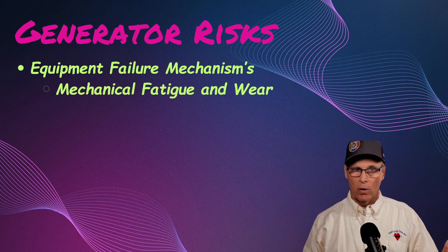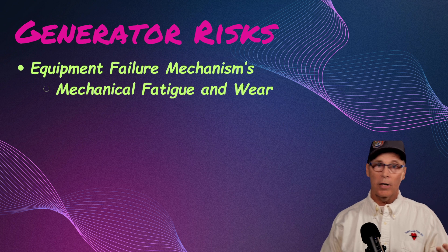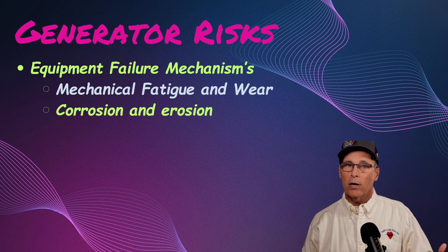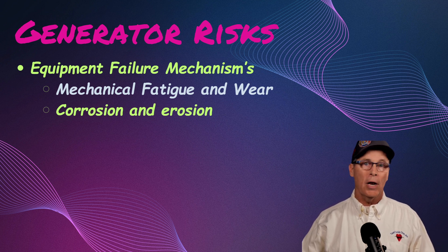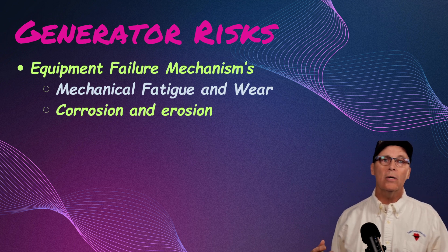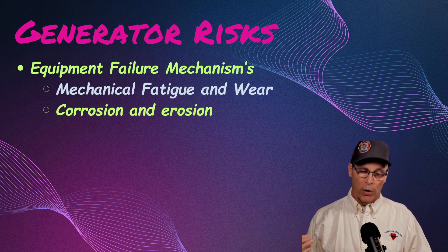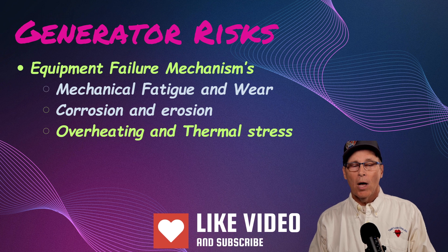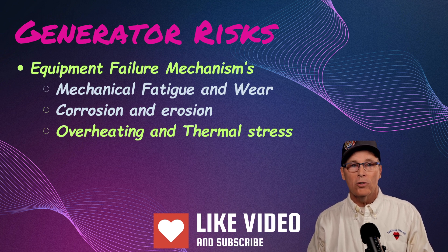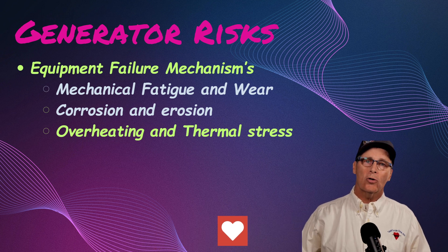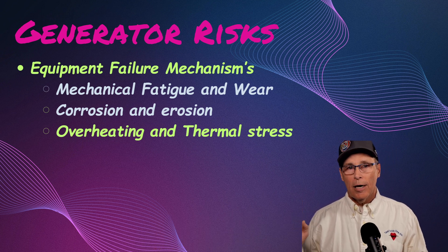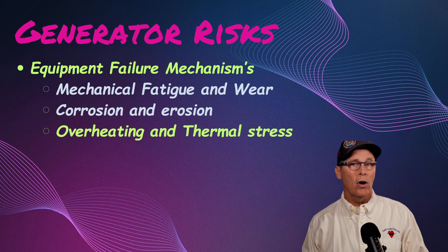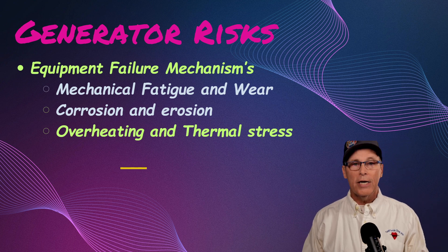Other causes of damage: mechanical fatigue and wear — every time units start up and shut down, they heat up and cool down and need to do so evenly. Corrosion and erosion — air-cooled units draw in lots of air, which can cause abrasion from dirty air, or corrosion from salt air near the ocean. Overheating and thermal stress — overloading a generator isn't common since most are sized for the generator step-up transformer, but in a chemical facility or refinery with on-site power generation, you can overload it.